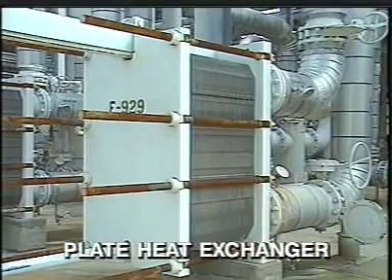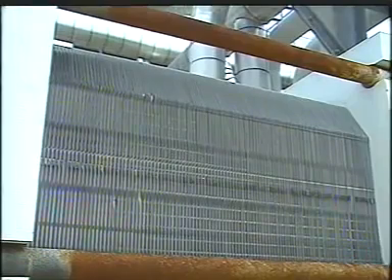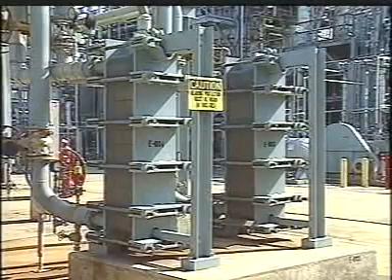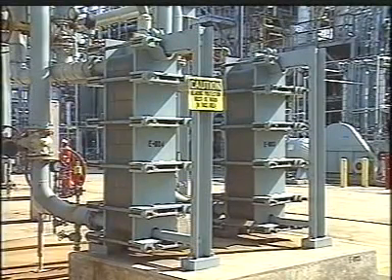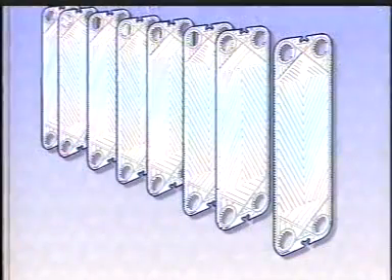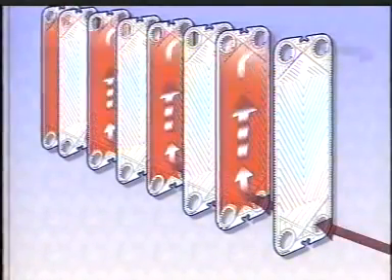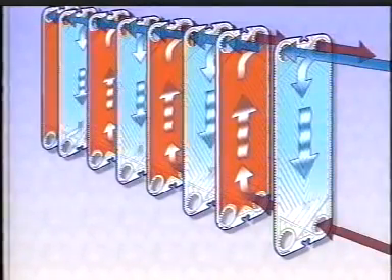This is a plate heat exchanger. Note its form and size. As its name implies, it's made of corrugated plates. The plates are held together with an external pressure plate that can be moved for maintenance and cleaning. Internally, fluids enter each plate compartment. The flow is set up so that the plates with hot liquid alternate with those containing cooler liquids.